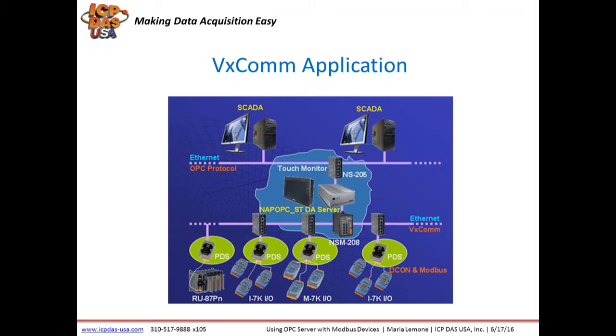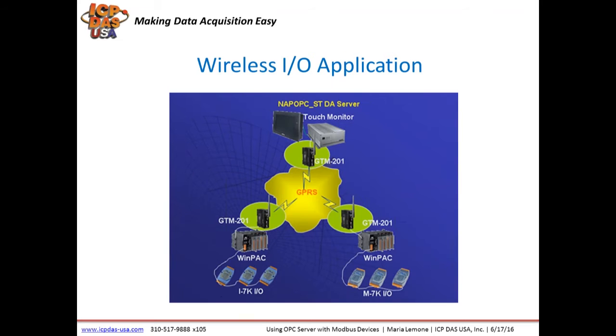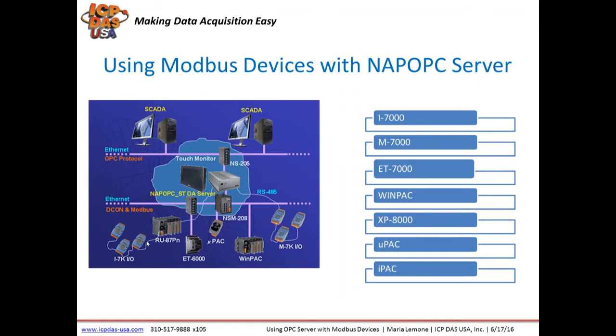VxComm is also supported with NAPOPC Server, so devices like our i7000, RS485, and also Modbus RTU-based modules can be connected to our PDS serial to Ethernet device servers, and those PDS devices can be connected back to Ethernet switches, which are connected to the NAPOPC Server running inside of a PAC or a PC.